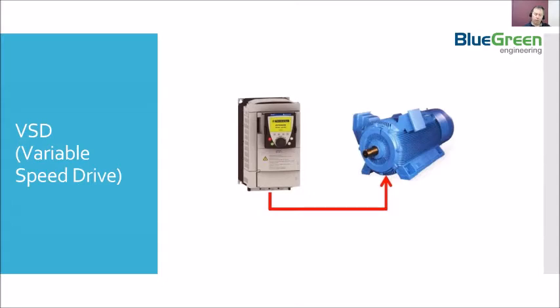Now, the relationship is not linear. So if we, for example, reduce the speed of a motor by 20%, and in many cases this will be enough to meet the demand, then the electricity consumption goes down by 50%. So the increase in performance, energy efficiency benefits and benefits to the environment are exponentially great, you could say.